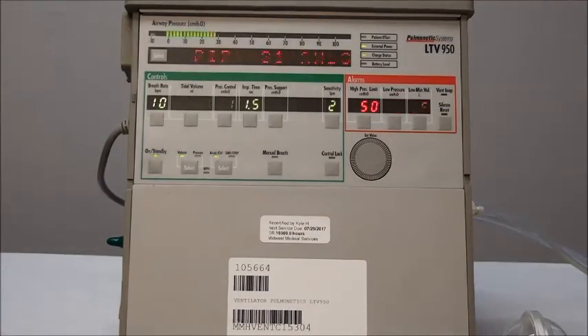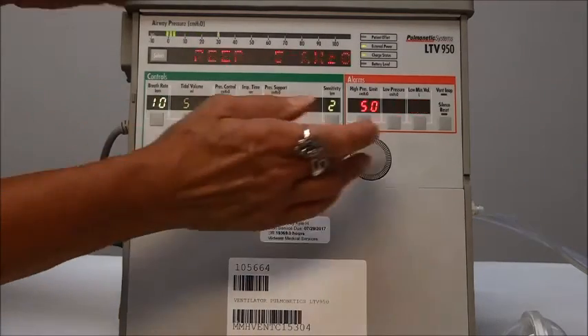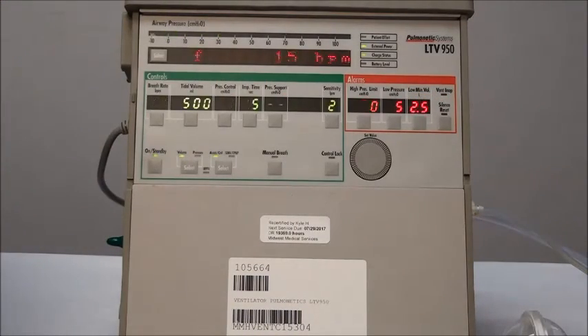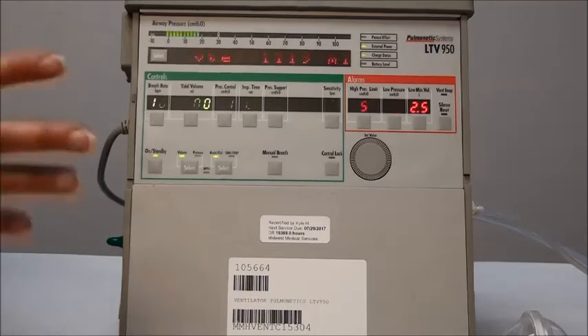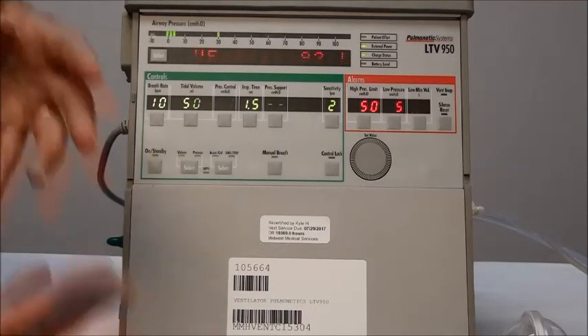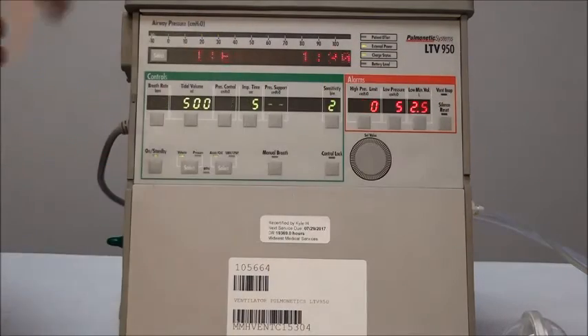Now, say you're going to suction your patient, you're going to disconnect your patient. That's going to cause the ventilator to alarm. You can go ahead and hit the silence, and that will silence the alarm for a minute, and that will give you time to do what you need to do. And then when you reconnect your patient, you can go ahead and reset the alarm again. If you don't solve your problem, or you're not done doing what you need to do within a minute, the ventilator is going to keep alarming. So if you just keep pushing the silence alarm, that's not going to solve your problem. It's going to quiet the alarm, but your patient's still going to have some sort of problem.